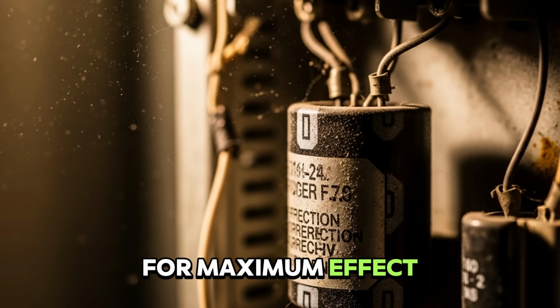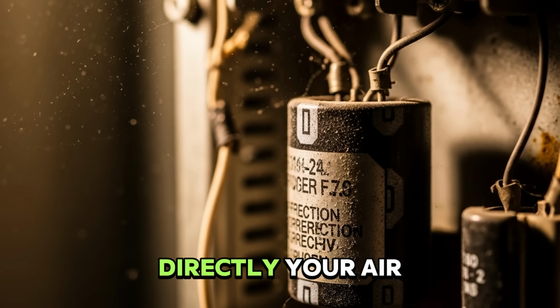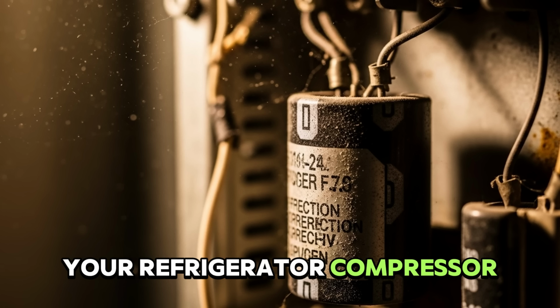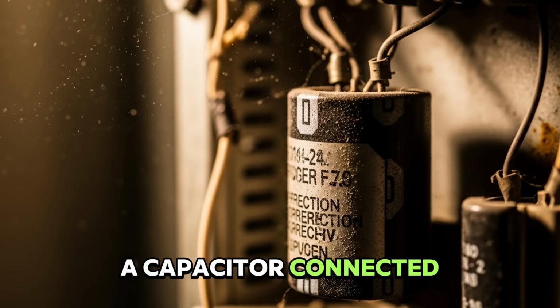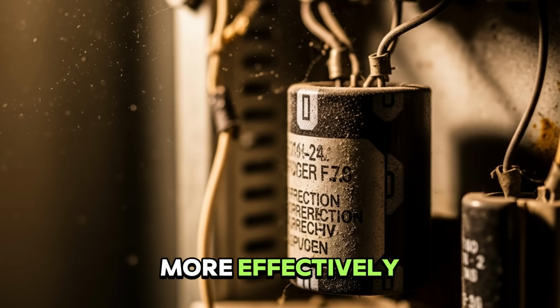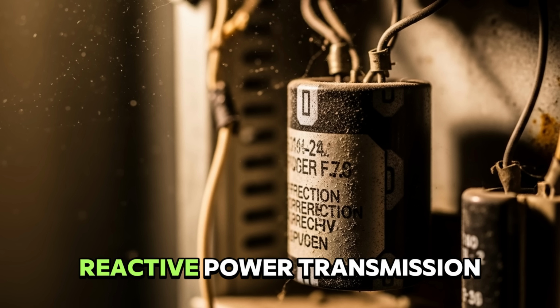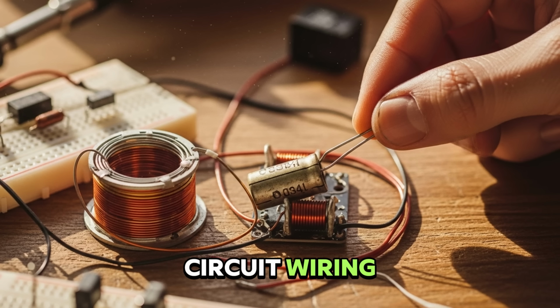For maximum effect, install capacitors near your largest inductive loads directly: your air conditioning unit, your refrigerator compressor, your electric water heater. A capacitor connected at the load point corrects power factor more effectively than panel level correction alone because it eliminates reactive power transmission through the branch circuit wiring as well.